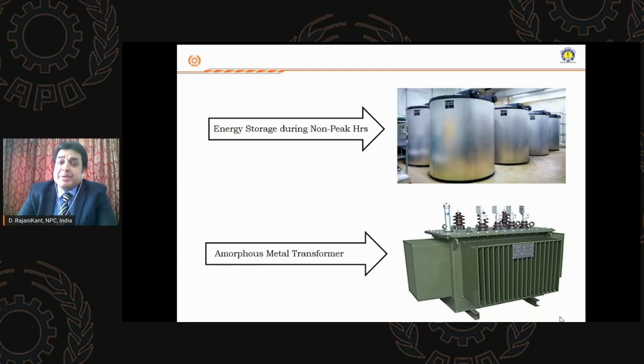So it is better always to run essential loads in peak hours and non-essential loads in non-peak hours. This has to be prioritized very clearly by the SME. Otherwise, a simple operation like water pumping, even that can be done in non-peak hours, as it is a non-essential activity. So you try to shift your peak hour consumption to non-peak hours, so that you will be reducing that 10 or 20% additional charge that is being levied per kilowatt hour.